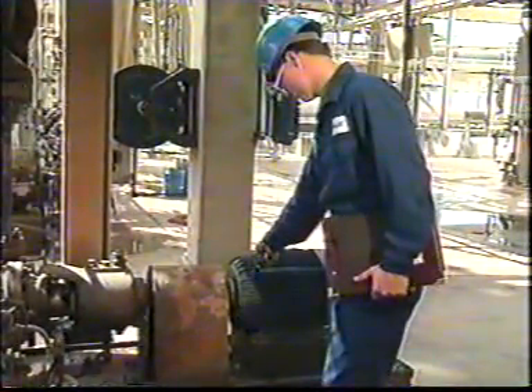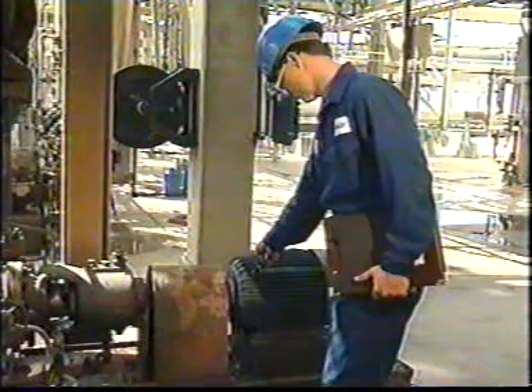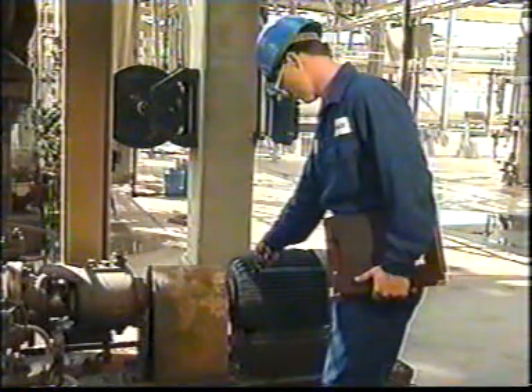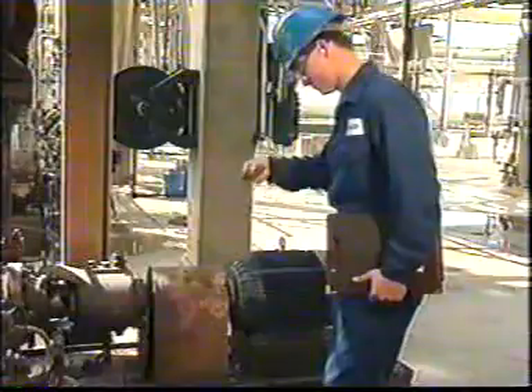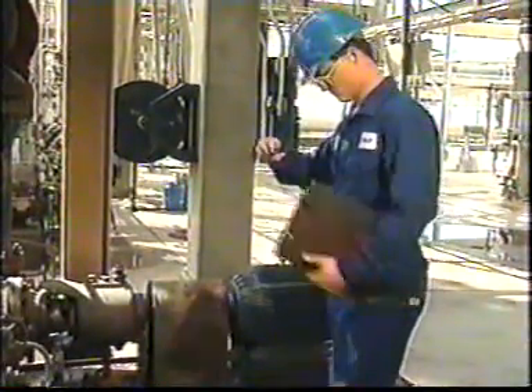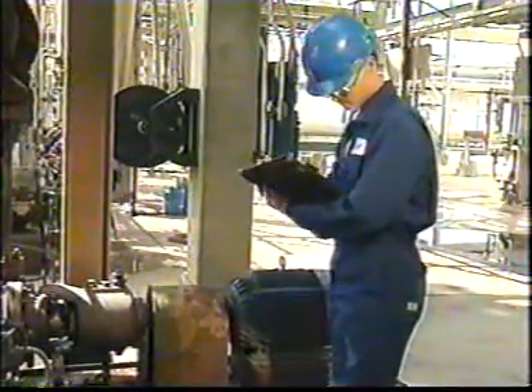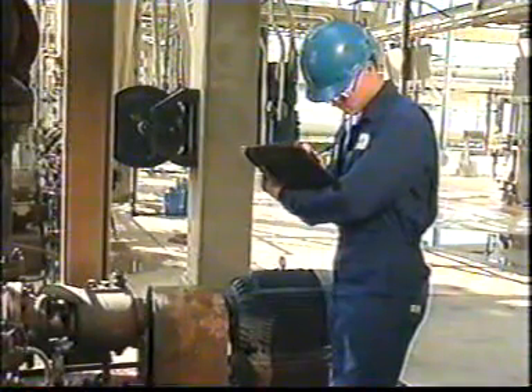Measurements taken for comparison over time need to be consistent. This means the sensor must be at the same location every time. Moving the probe even a few inches can result in very different vibration readings. One way to ensure removable sensors are reading the same location is to mark the spot with paint, weld a small flat disc, or drill a spot in the machine case.